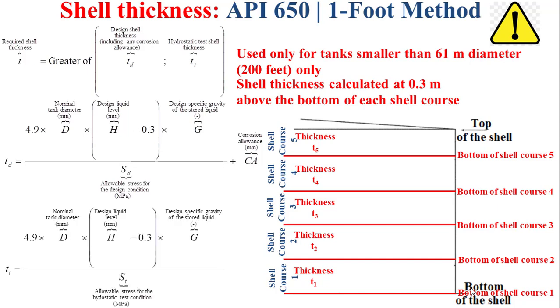The hydrostatic test shell thickness tt is determined as a function of the nominal tank diameter D, the design liquid level h, the design specific gravity of the stored liquid g, and the allowable stress for the hydrostatic test condition denoted by st.